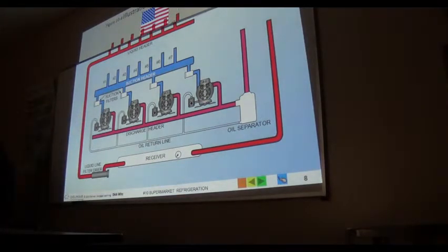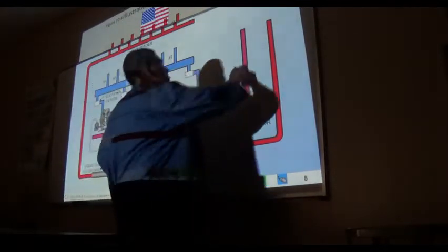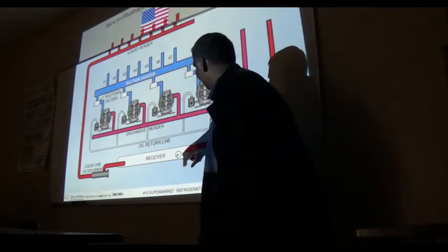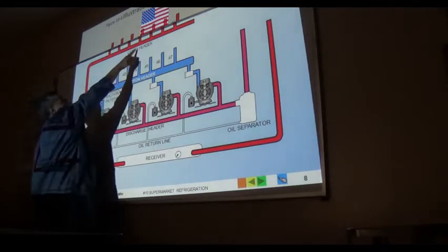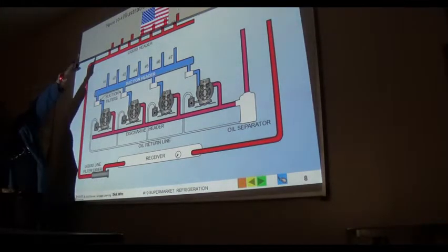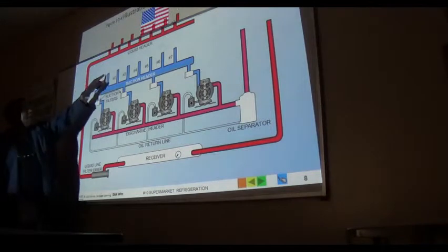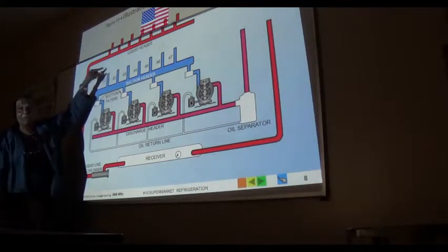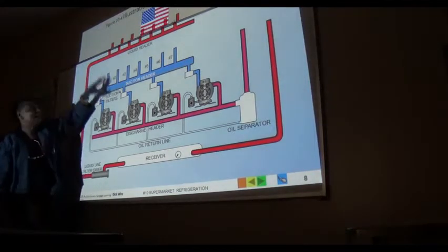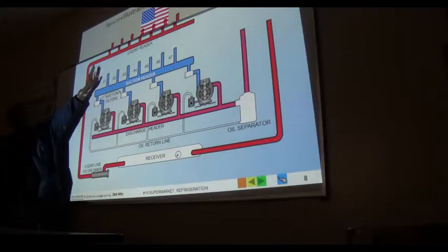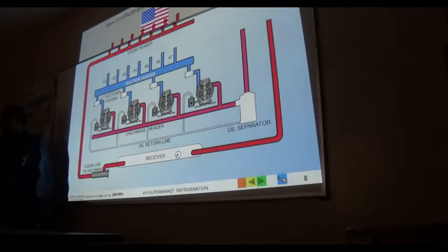The receiver comes back from, you got this, the liquid header. This goes to the condenser coil, right? That vapor comes back as liquid into the receiver. Goes through the liquid line filter dryer into my liquid header. Back in, and that goes to all the evaporator metering devices. Right here, at this point, if I need it, I will have my evaporator pressure regulators as well as my liquid line solenoid. And your metering not here, sorry, up here. Your metering device will be on top.